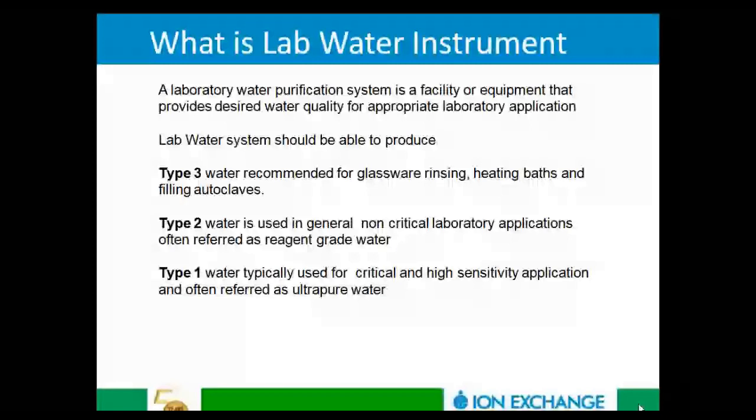For example, an autoclave or a sterilizer in a hospital would need a well treated water which would avoid scaling on the heaters, due to which the heat transfer may be reduced.